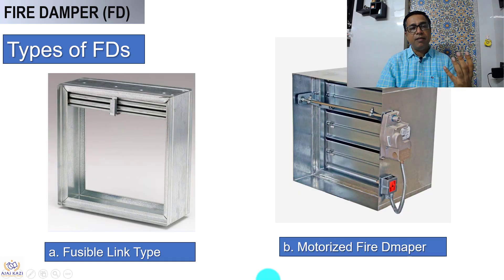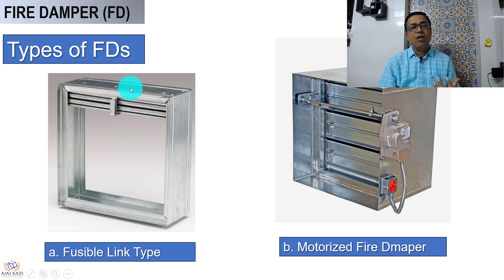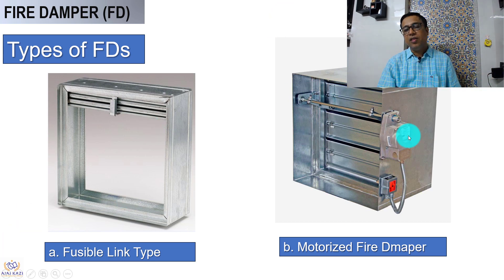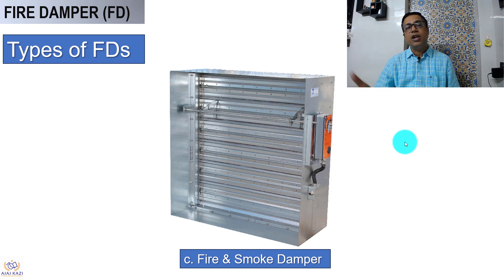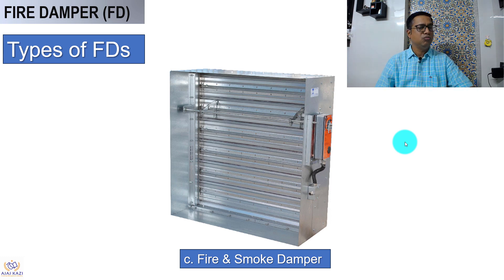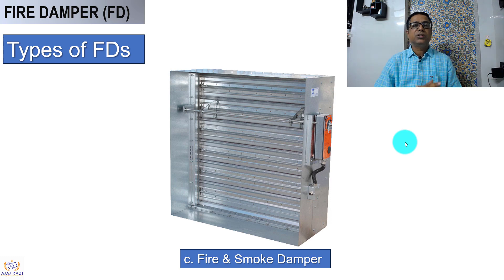There are types of fire dampers. The first is the fusible link fire damper — specifically a curtain-type fusible link fire damper. In case of fire, the link collapses and the curtain drops down, preventing fire from passing through. Another type is the motorized fire damper, which has a motor that receives a fire signal from the zone and closes accordingly. There is also a fire and smoke damper with a dual actuator that also senses smoke, preventing smoke from passing from one side to the other.